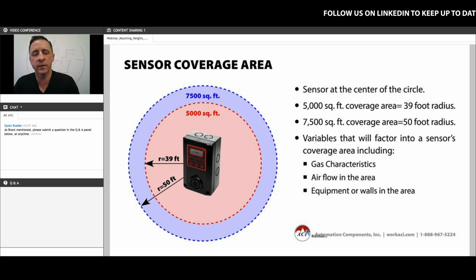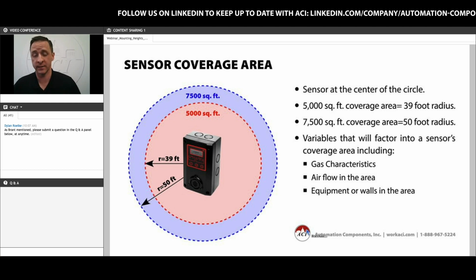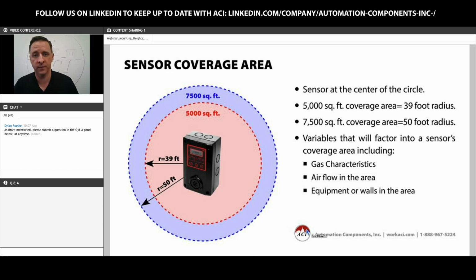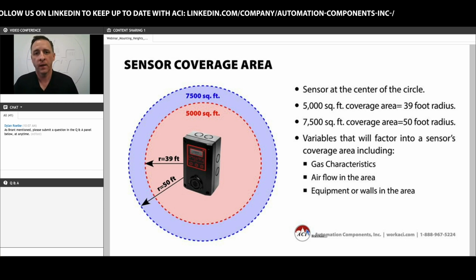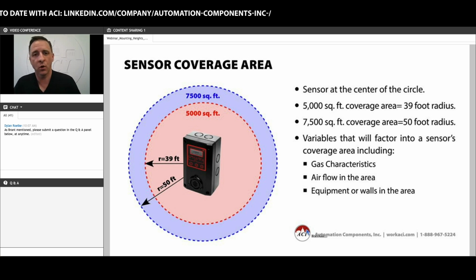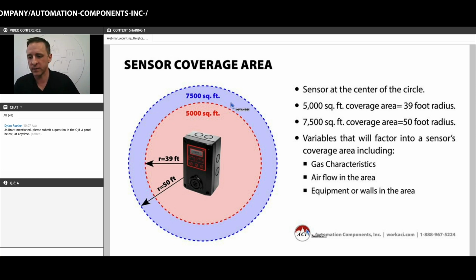Some other variables will go into consideration when determining gas sensor placement and coverage areas, and those are the characteristics of the gas. A very heavy gas like a Freon is not going to disperse and fill the space as quickly as a lighter gas like hydrogen or helium. The overall airflow in the space matters too. If it's a garage with multiple entrances and exits and multiple windows or vents, you may need fewer sensors to cover that space. In an underground parking garage where you have pillars or low ceilings and limited entrances, you might need more sensors to cover that space.